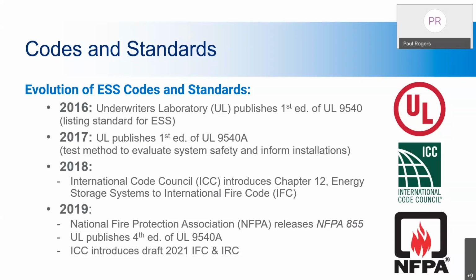In 2019, the NFPA released NFPA 855. I mentioned before about the 2021 IFC and NFPA 855 - the same committee, or most of the same committee that worked on NFPA 855, also worked on the 2021 IFC, so they were aligned very closely. If you did a side-by-side comparison, you'd see what I'm talking about. They also brought out that you need to test your batteries up to UL 9540A, and you can see that UL has published that fourth edition of 9540A. The ICC draft of 2021 also included the International Residential Code.